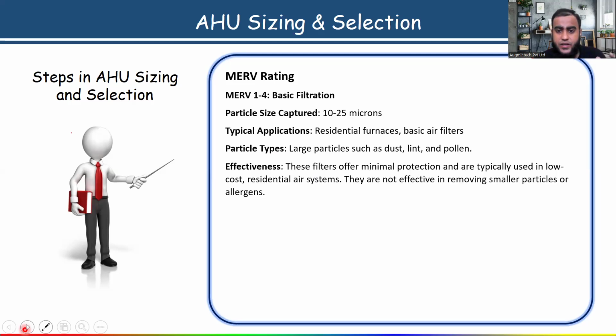Effectiveness is given: these filters offer minimal protection and are typically used in low-cost residential air systems. They are not effective in removing smaller particles or allergens. So for that, you have to select a different MERV rating. I'm showing you each and every rating. MERV 5 to 8 rating filter is better filtration, and it can capture 3 to 10 microns.